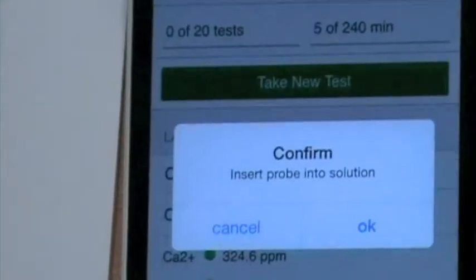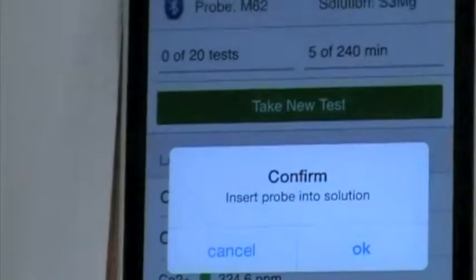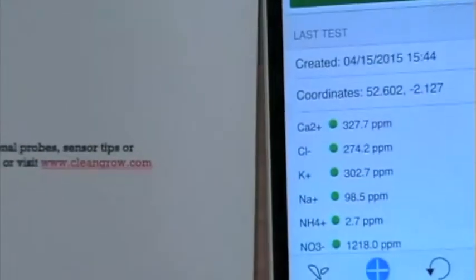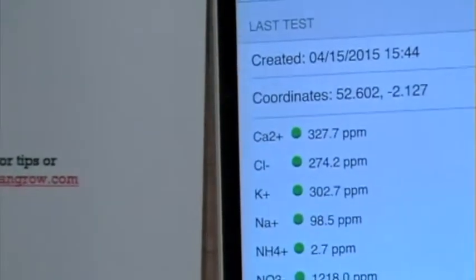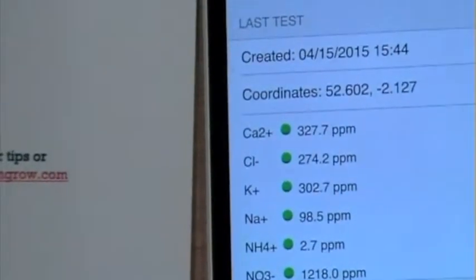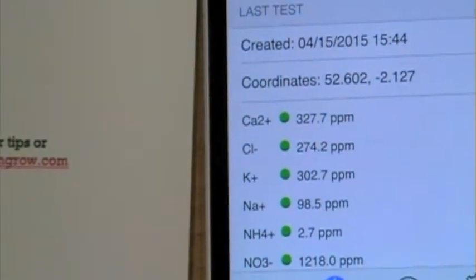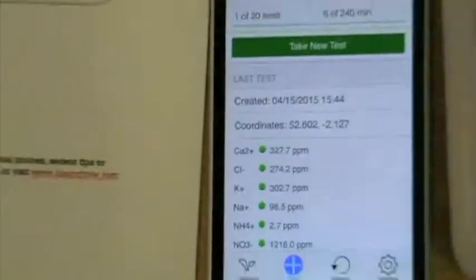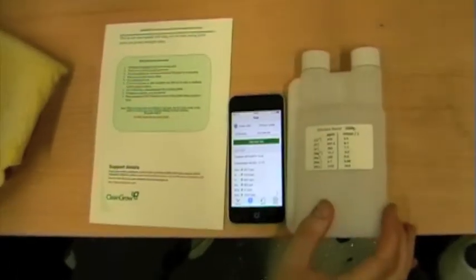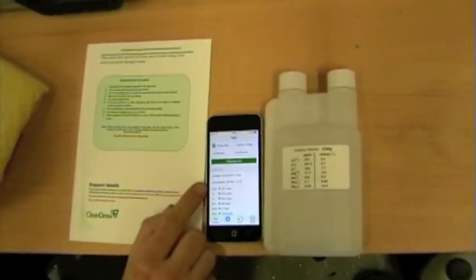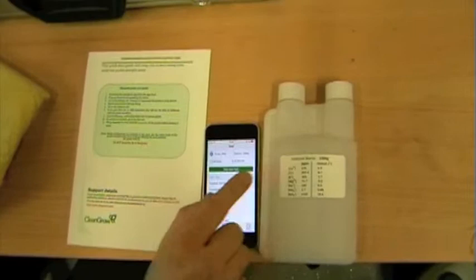Okay. Insert probe into solution. That's already done. Okay. Go ahead. Now it will take a minute again. 1 minute, 60 seconds exactly. So you'll see the results appear on the screen. And there you go. You can always compare that to the back of the bottle of the calibration solution 2. Should be similar if everything's gone well.